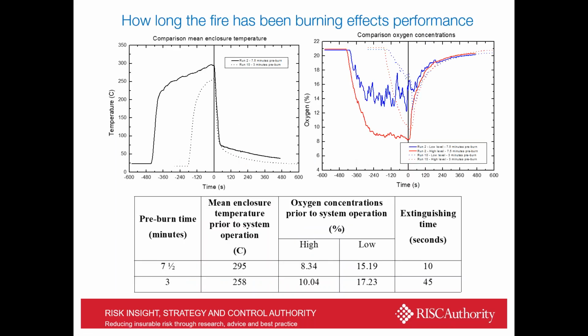So if we look at how long the fire has been burning, how that affects performance, there are two graphs here. On the left, we have the temperature in the enclosure. T0 is when we release the Watermist system. And on the right, we see the oxygen in the compartment itself. There are two oxygen sensors in there. And what we have here is two fires which are identical, ventilation conditions which are identical. The only difference is that we allow a pre-burn time, if you like, a detection time of the fire, to be longer for one fire than the other. And you see that in the solid black line on the left-hand graph.